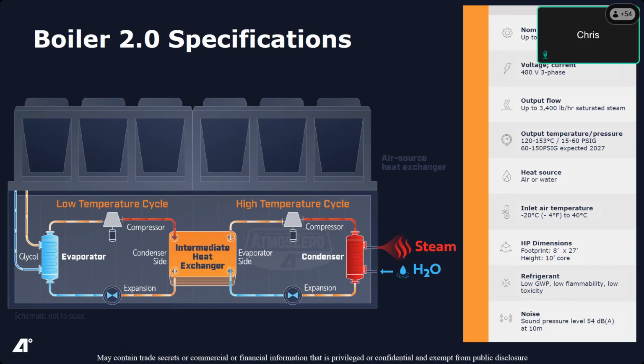So I mentioned, if we go from the top to the bottom, we are a 1 megawatt thermal system. We can do a little bit less. So in the case of a building where you have like a 15 PSI system, just based on how the math works out, it's a little less than a megawatt. It's probably closer to like 850, 875 kilowatts.